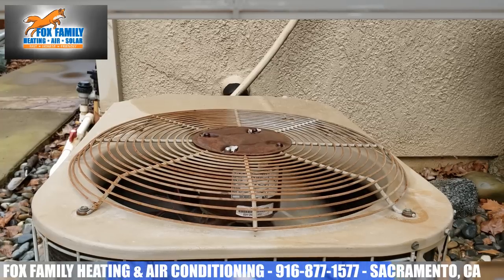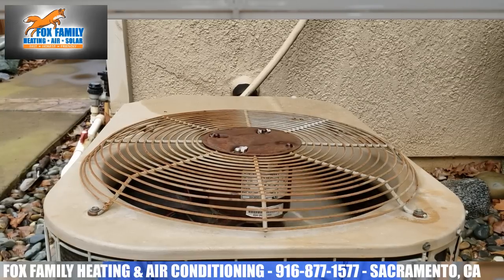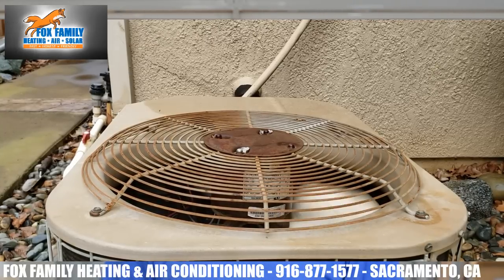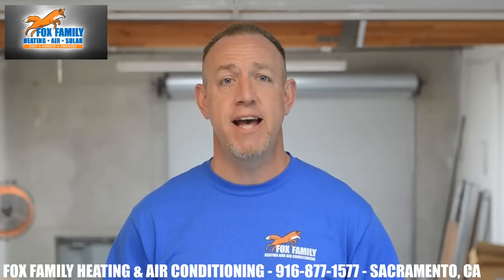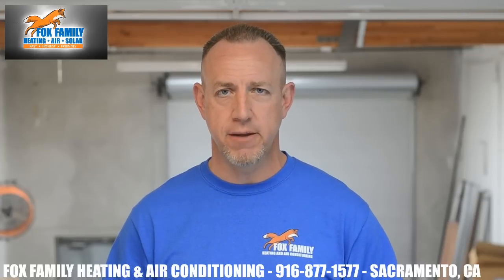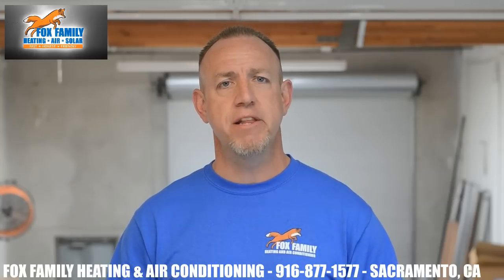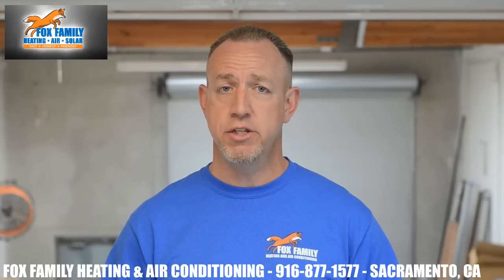The fan blade is protected by a round metal shroud that allows warm air to flow out and protects people from getting their fingers inside the AC. Sometimes this shroud starts rattling as the screws that hold it down start vibrating loose, possibly creating a larger hole than the screws were initially sized for. The solution is to install slightly wider screws to hold the shroud down more securely. Another trick is to use little rubber isolation pads as shims to dampen the vibration between the shroud and the frame of the AC, which can really help reduce rattling noise on an aging system.